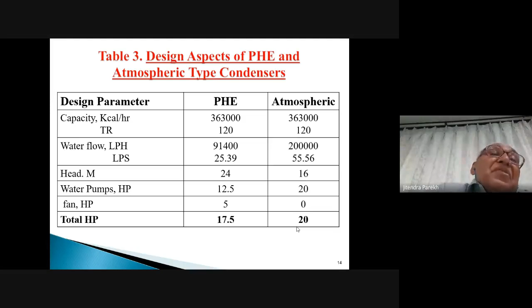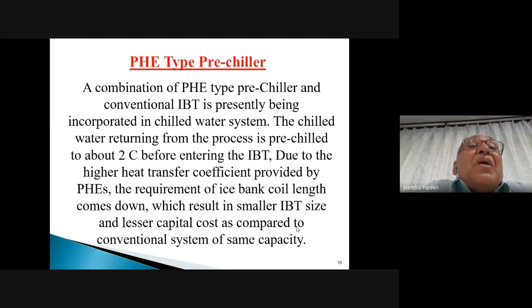Now, in the IBT system also, in the conventional type, you don't generally use this PHE type of pre-chiller, which is also very useful when chilled water is returning from the process. If you put in the pre-chiller and cool the chilled water down to 2 degrees centigrade before it enters the IBT, due to the high heat transfer coefficient provided by the PHE, the requirement of ice bank coil length comes down, which results in a smaller IBT size and lesser capital cost as compared to a conventional system of the same capacity. So I would suggest that we should use the PHE type of pre-chiller system in IBT systems.